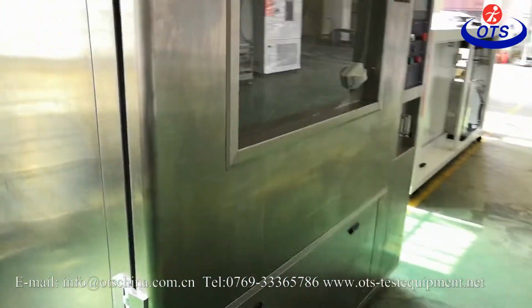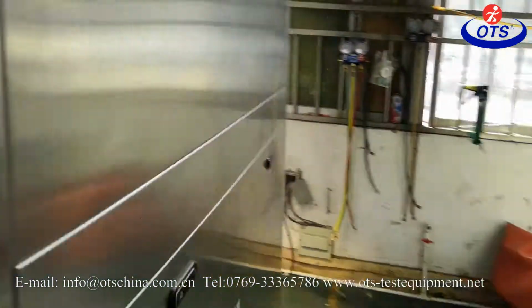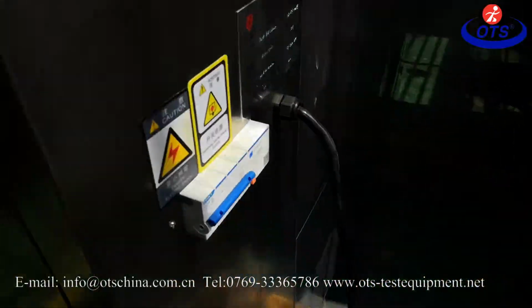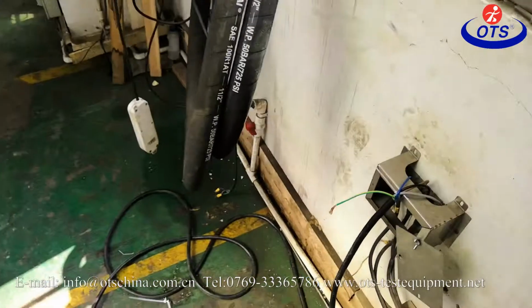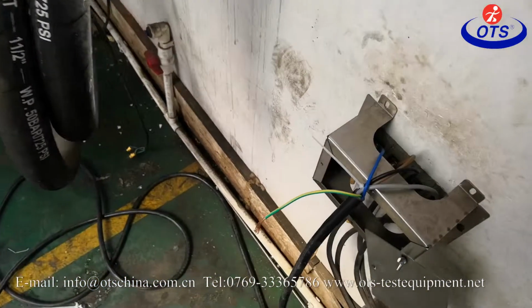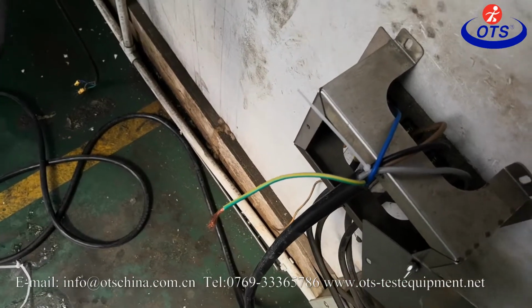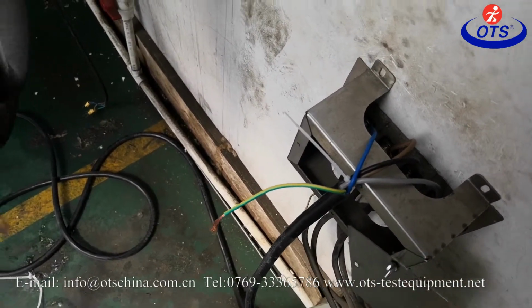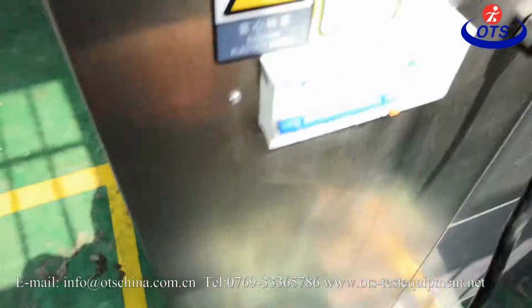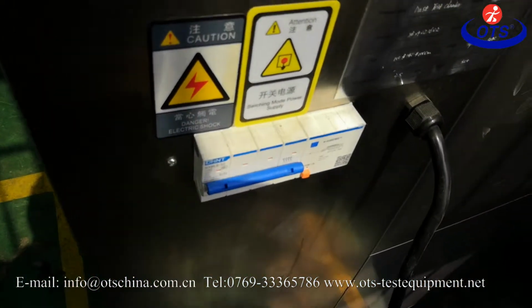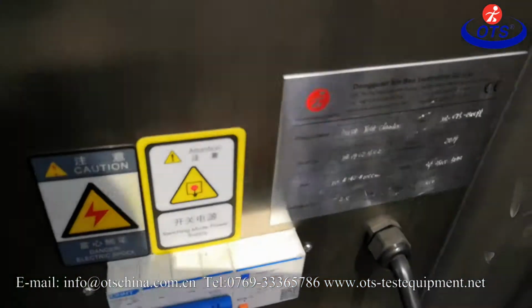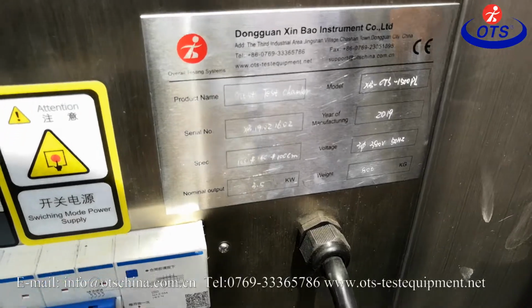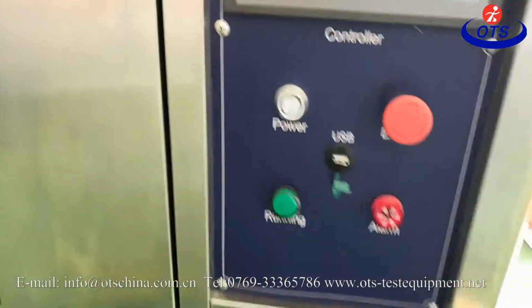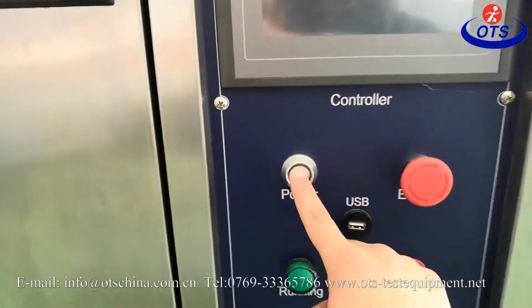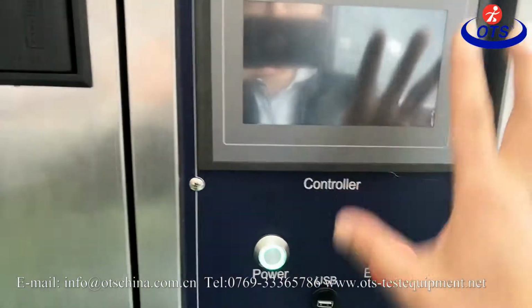First, of course, we need to connect the power. The power for this dust test chamber is three phase, 5 lines. So first, connect the power. Second, open the power switch, the main power switch. The next one, of course, open the power switch from the control panel.